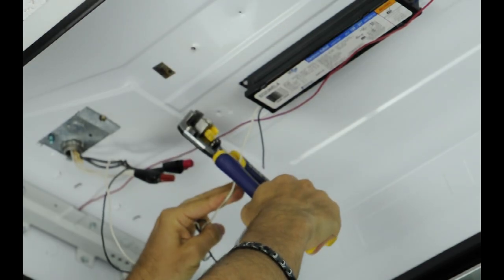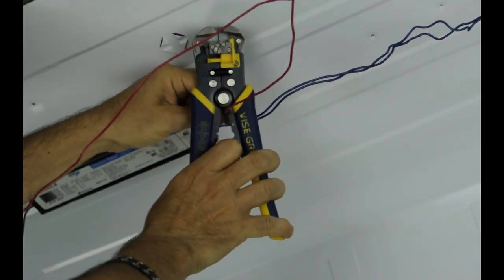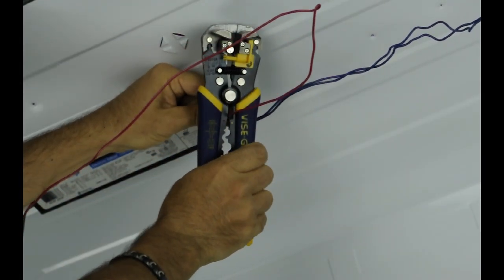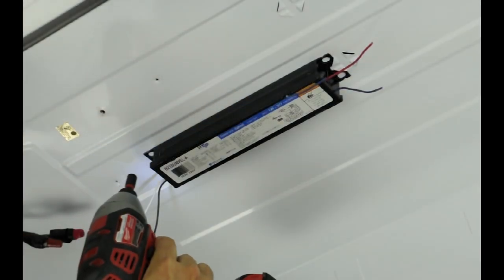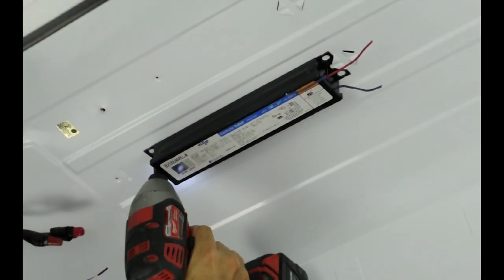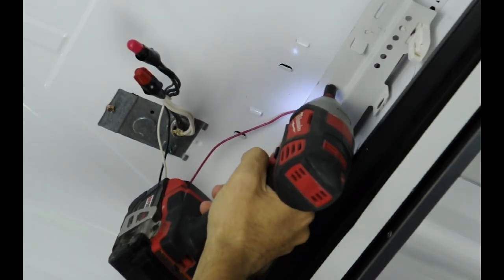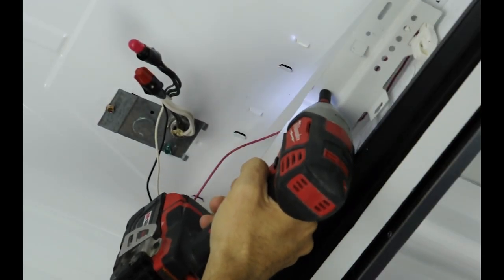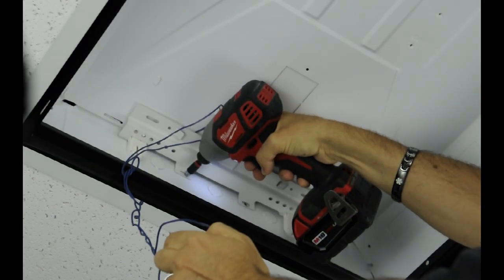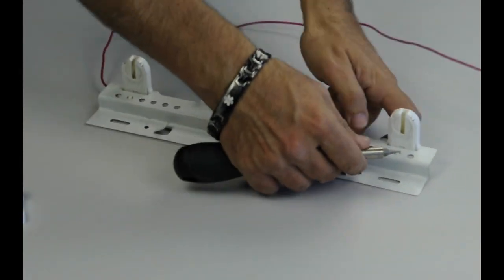Cut all ballast wires and remove the ballast. Remove the tombstone brackets. Remove the shunted sockets on both brackets.